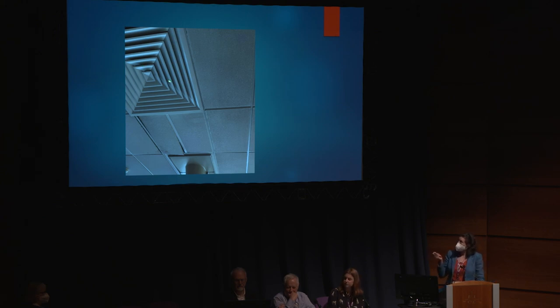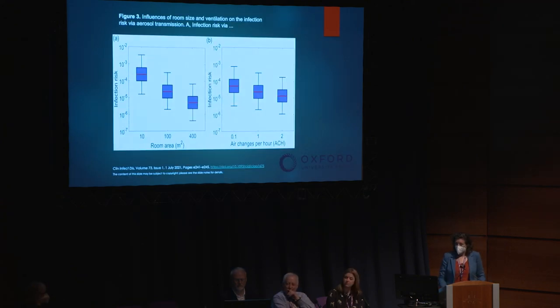Theater outbreaks are very well established in the literature. Here's one in an ITU - you can see air coming through a ceiling tile that's falling down, with lots of dust in there. The air movement is entraining along here because it's coming from the diffuser, picking up stuff into an ITU setting. Am I being fussy, or is this science? This is science - it's saying that by not paying attention to clean air, you're increasing the probability of a potentially catastrophic infection.